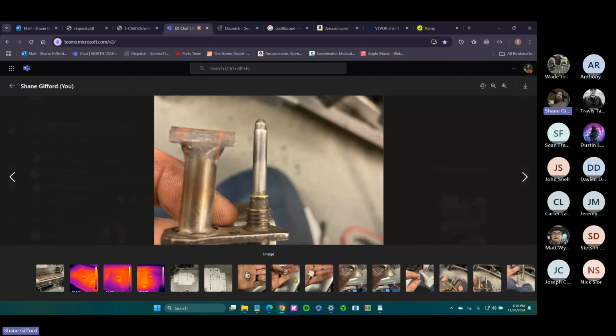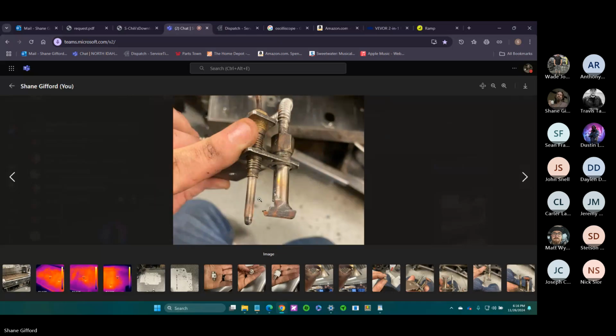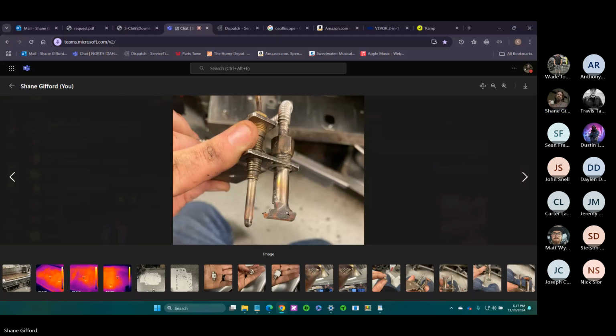So as carbon and soot builds up, it's going to definitely inhibit this thermocouple rod's ability to create volt DC. So this right here would be an indication of we keep losing our pilot, or it won't stay lit. The gas valve goes out. Pilot won't stay lit. Pilot won't light. This is that guy that generates that DC voltage. You got your flame coming up from your pilot line. It hits the hood, and that flame is just tagging this thing 24/7.